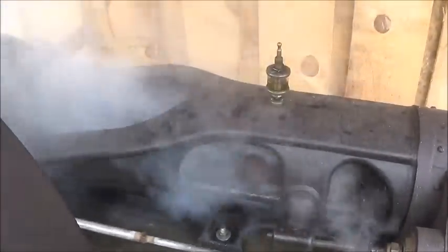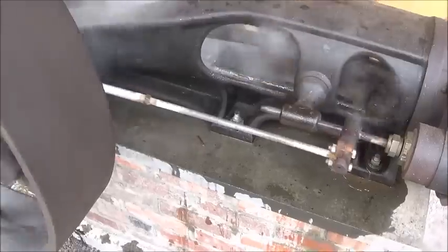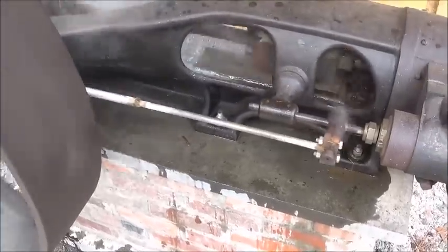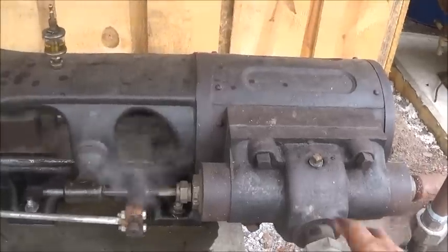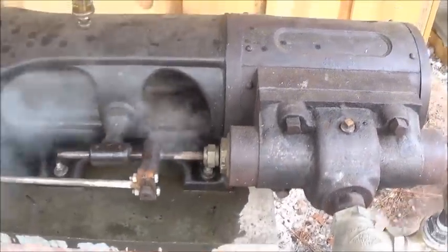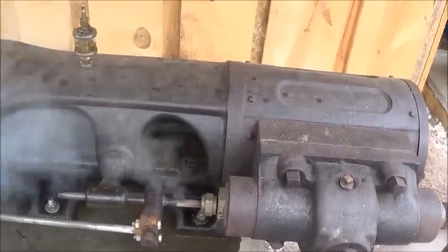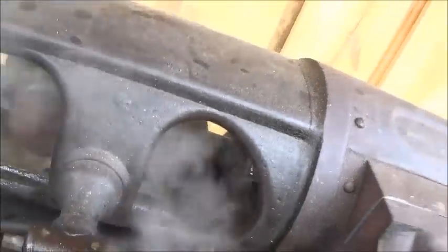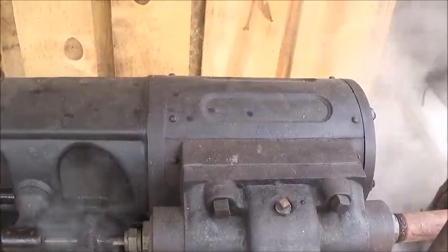So, I think the main thing on this one, let's cut back here. Okay, our noise, I believe, is in our valve. Pretty sure that's the noise I'm hearing. I got to take that back apart, and we may never get that out of it. But we've got a bad leak on that packing on the rod that we're going to have to work on.